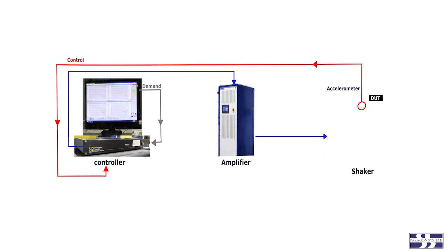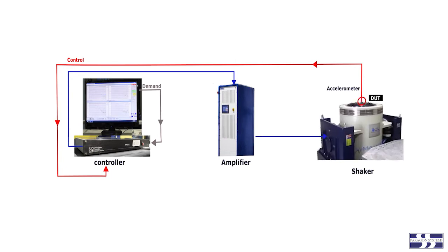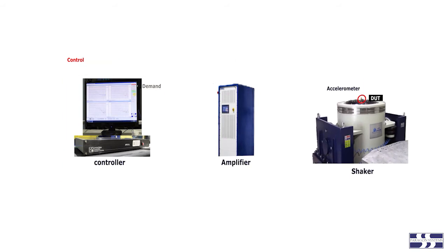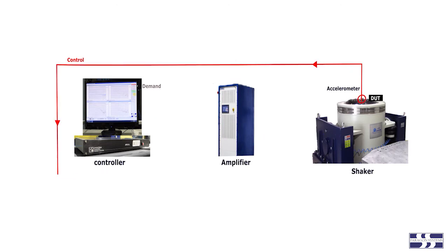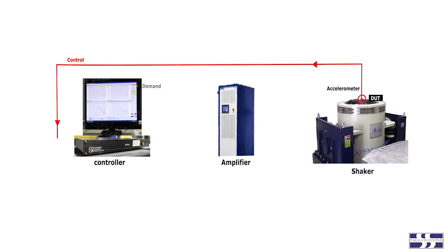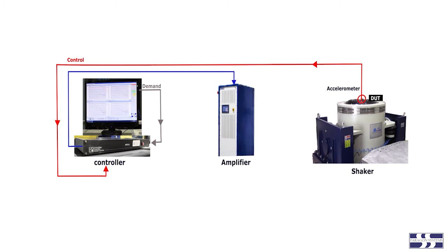The amplifier output drives the mechanical movement of the armature, which is sensed by the accelerometer. The controller compares the new accelerometer signal to the test profile and continues to adjust the amplifier drive signal in a closed loop until the accelerometer signal matches the test profile. This control loop cycle can occur at up to 50 kHz.